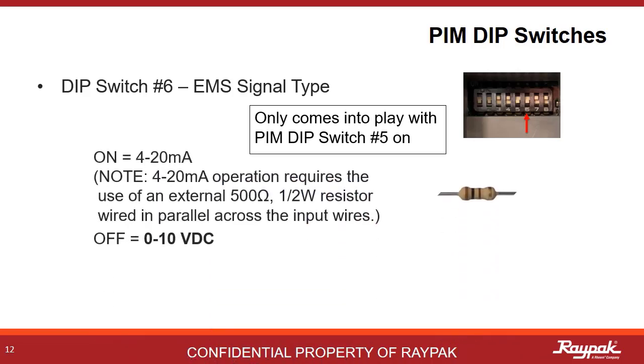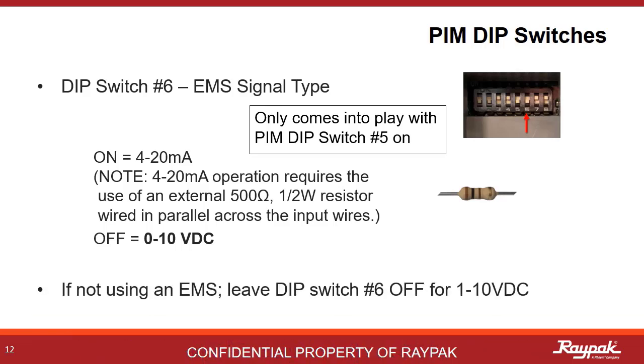Dip switch number six only comes into play when dip switch number five is on. Here's where you select what kind of signal is needed. On indicates a 4 to 20 milliamp signal, while off indicates a 0 to 10 volt DC signal. If not using an energy management system, leave dip switch number six on the PIM off.